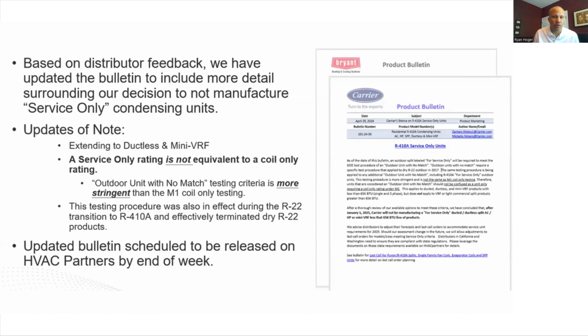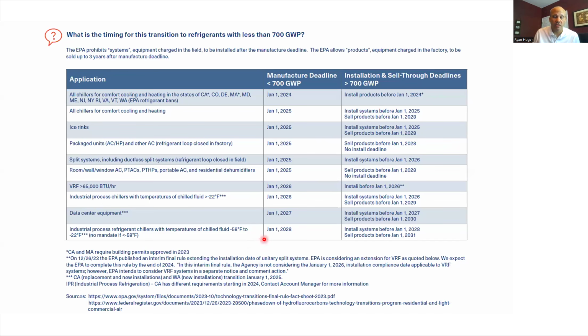I don't know if I have a slide for it, but the first loophole is that the manufacturer can continue to produce 410A evaporator coils for use with furnaces indefinitely. There's no end date for that. So if 15 years from now, Carrier wants to make an evaporator coil for you guys to put on some old 410A unit for warranty or service reasons or whatever, they can do that. There's no cutoff date for the evaporator coil.